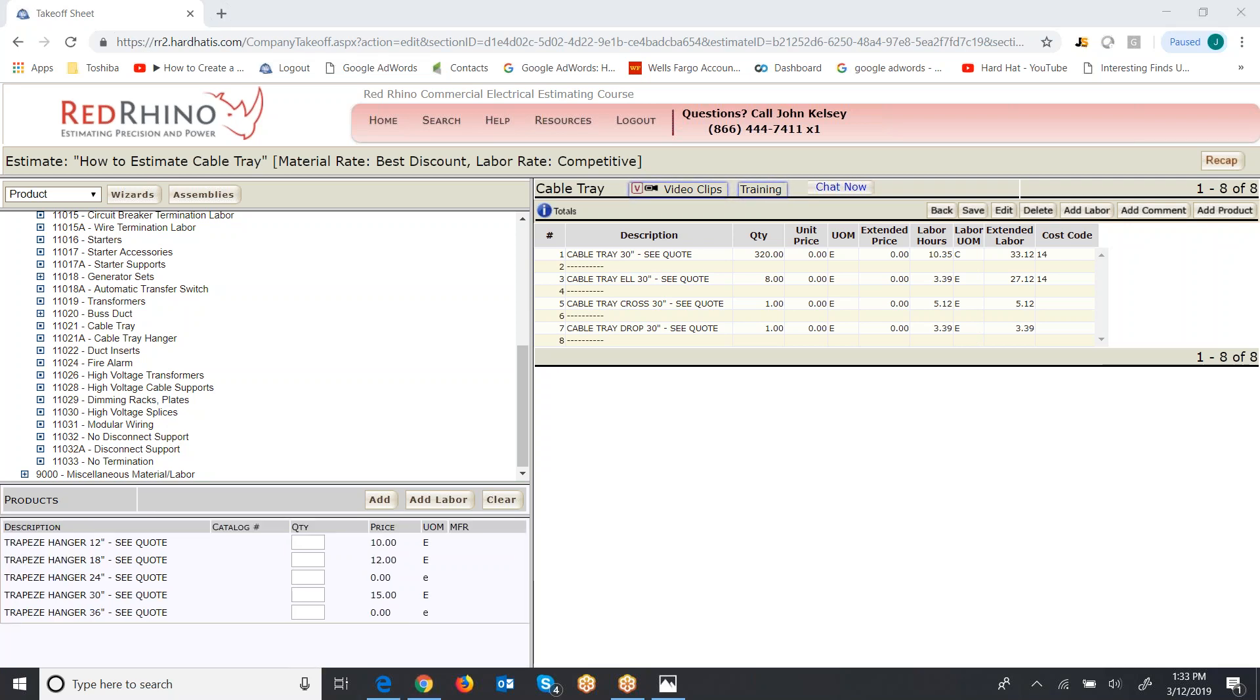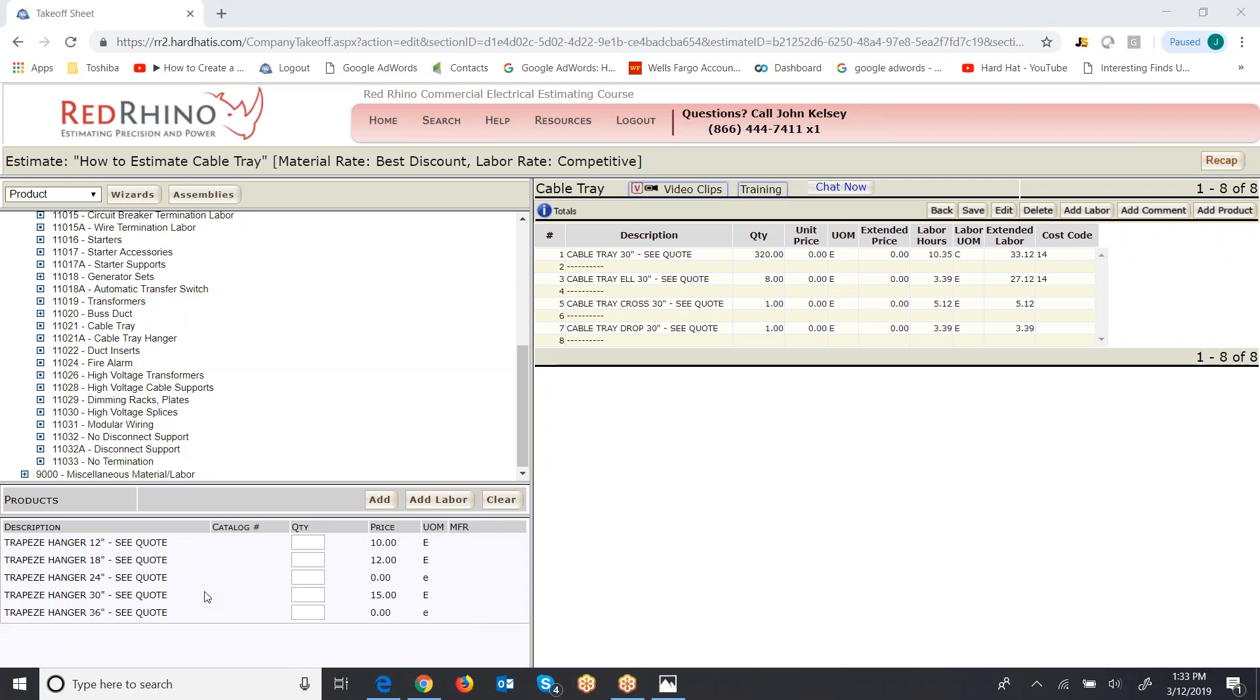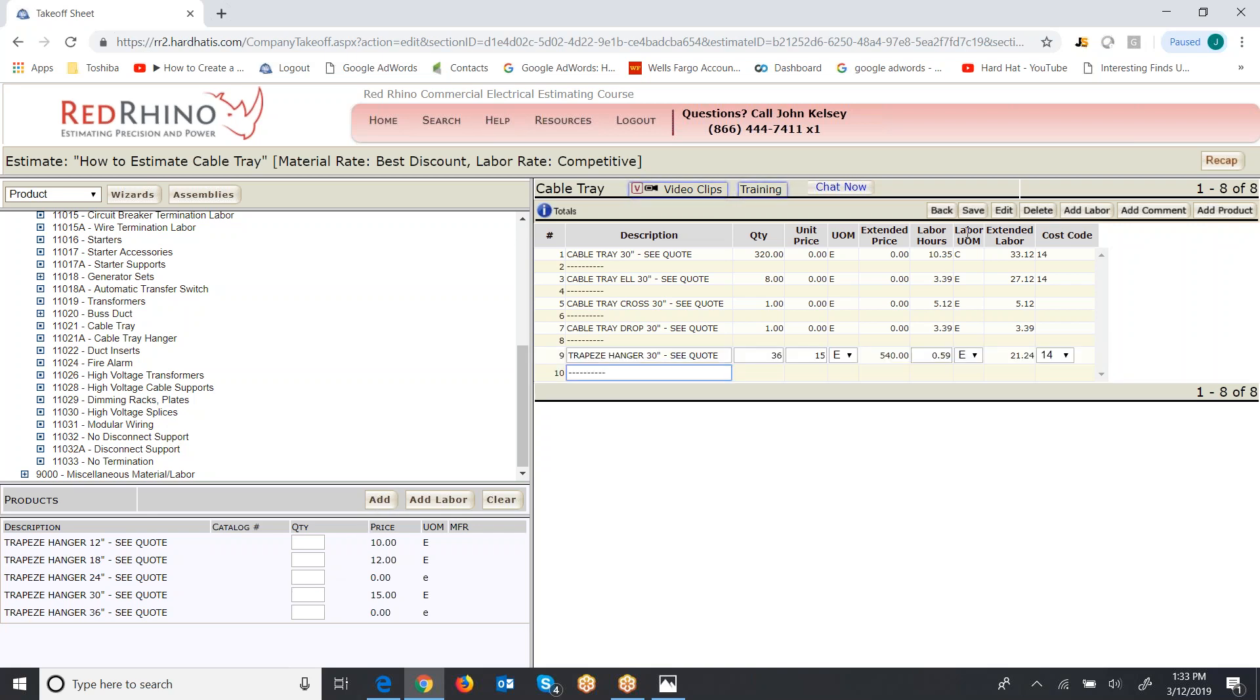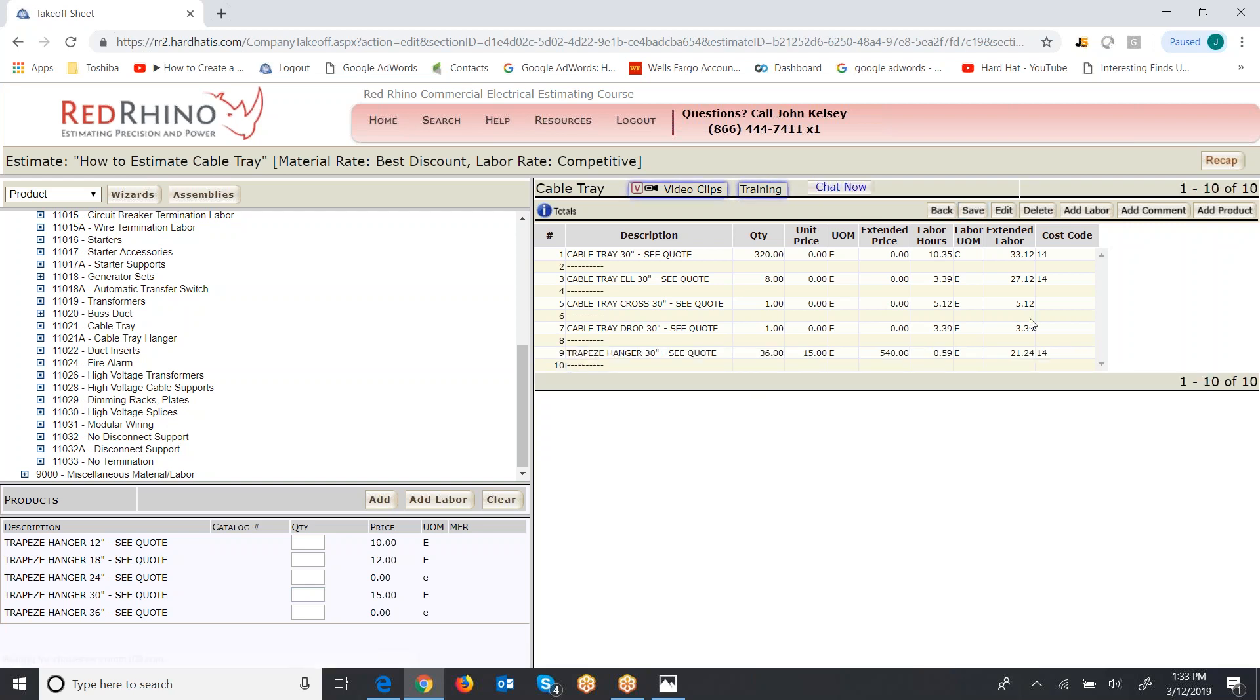Now, the other thing is I've changed the screen here. I've clicked on cable tray hangers. So it also has hangers for each of these different sizes. I put in about 320 feet. I'm going to put a hanger every 10 feet. So I'm going to put 32 with a couple extra. I'm going to make it 36 hangers. Just put the quantity in here, click add and it populates to the right. And I click save.